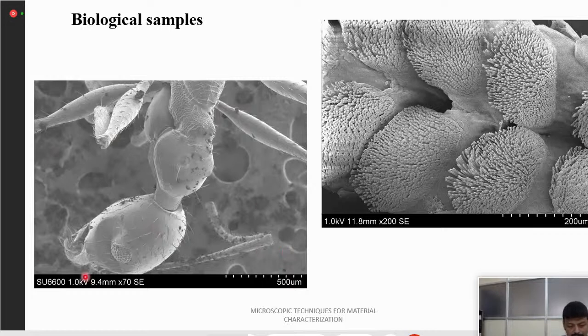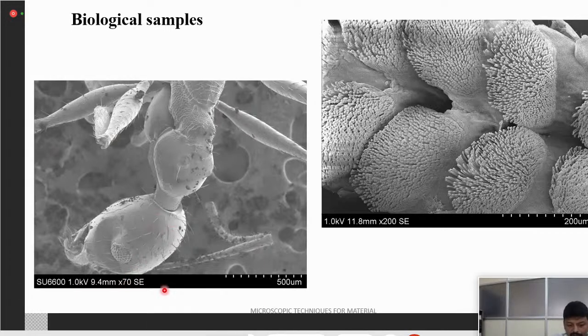So the first one has an acceleration voltage of 1 kV. Because this is a biological sample, we are applying only a lower acceleration voltage, only 1 kV. This is the working distance, 9.4 mm. We can change it from 40 mm down to 5 mm, even 3 mm. This is the magnification, 70x only. This can even be seen with our eye, so that's why it's 70x only. SE means secondary electron imaging. If you are doing BSE, this will be replaced.